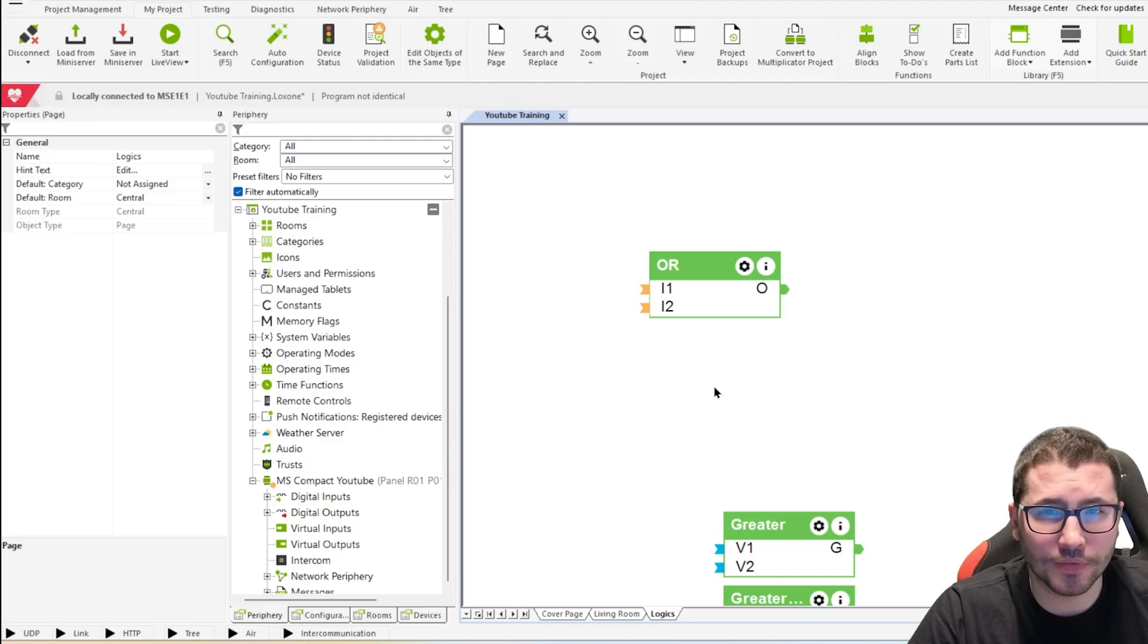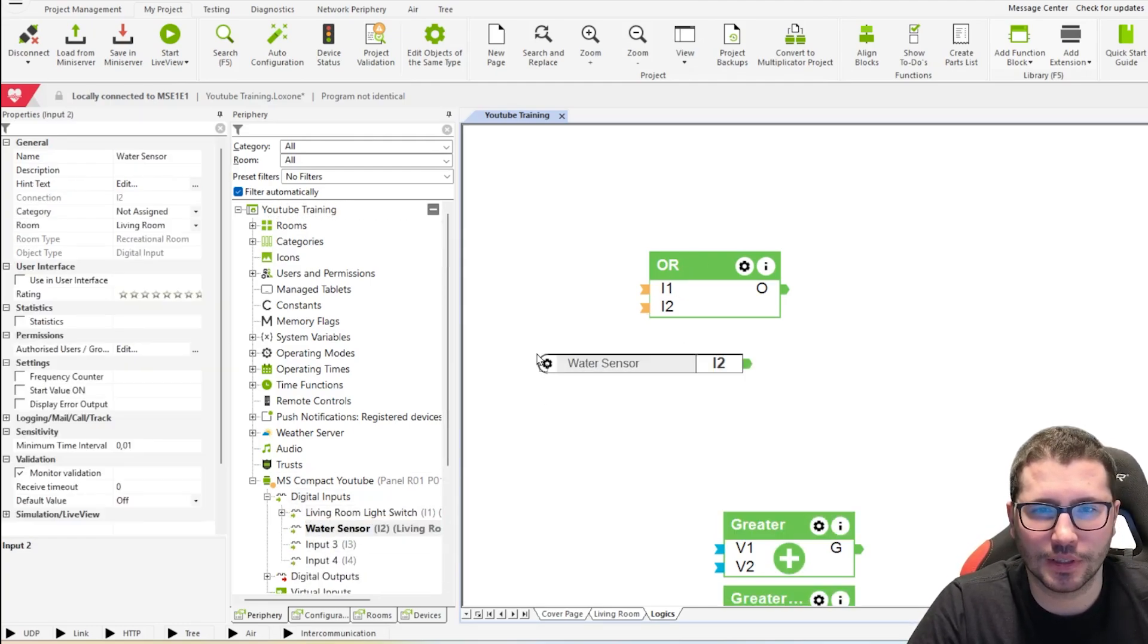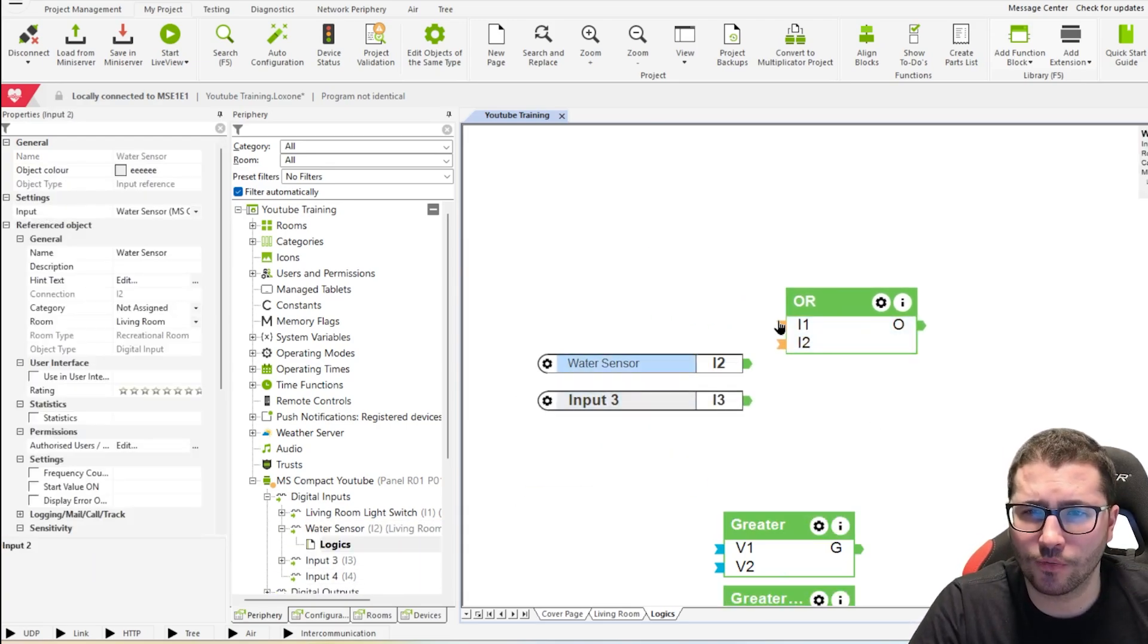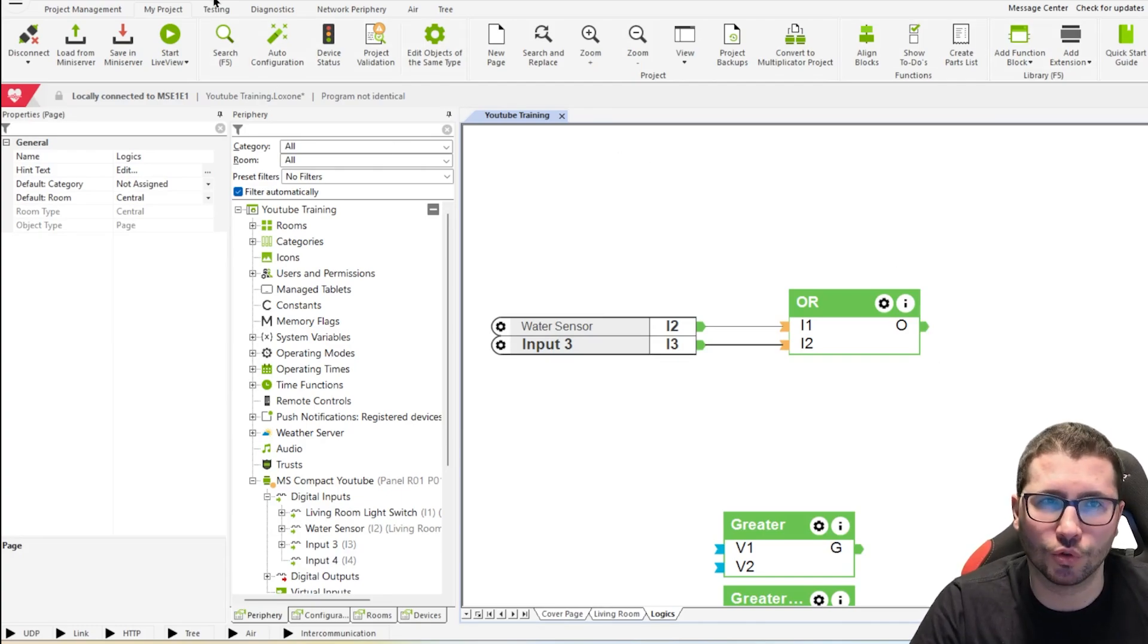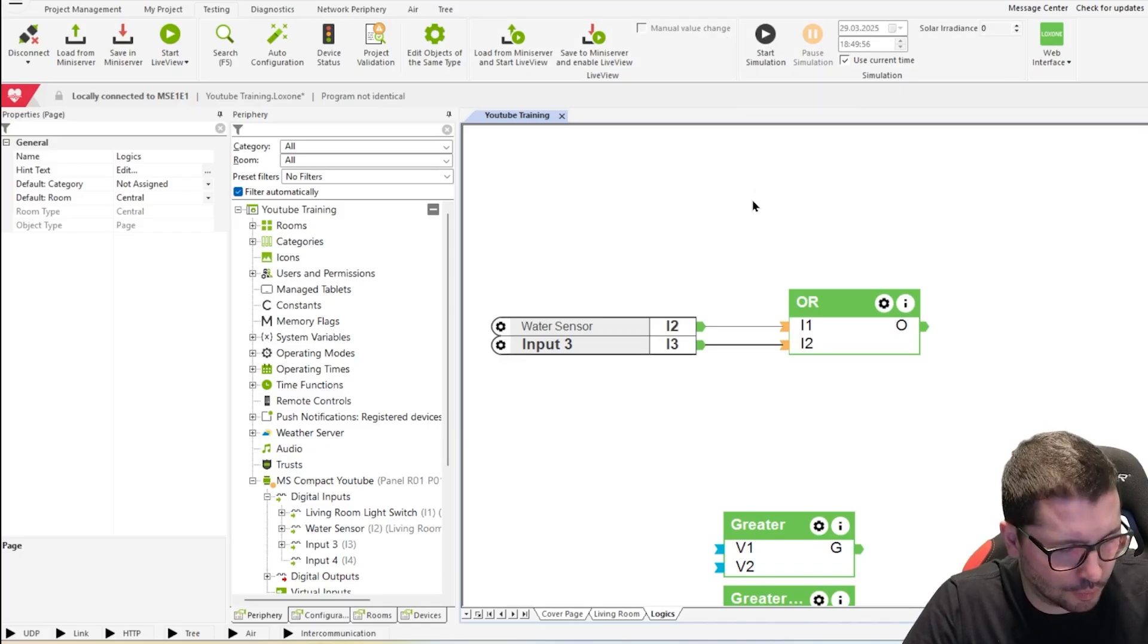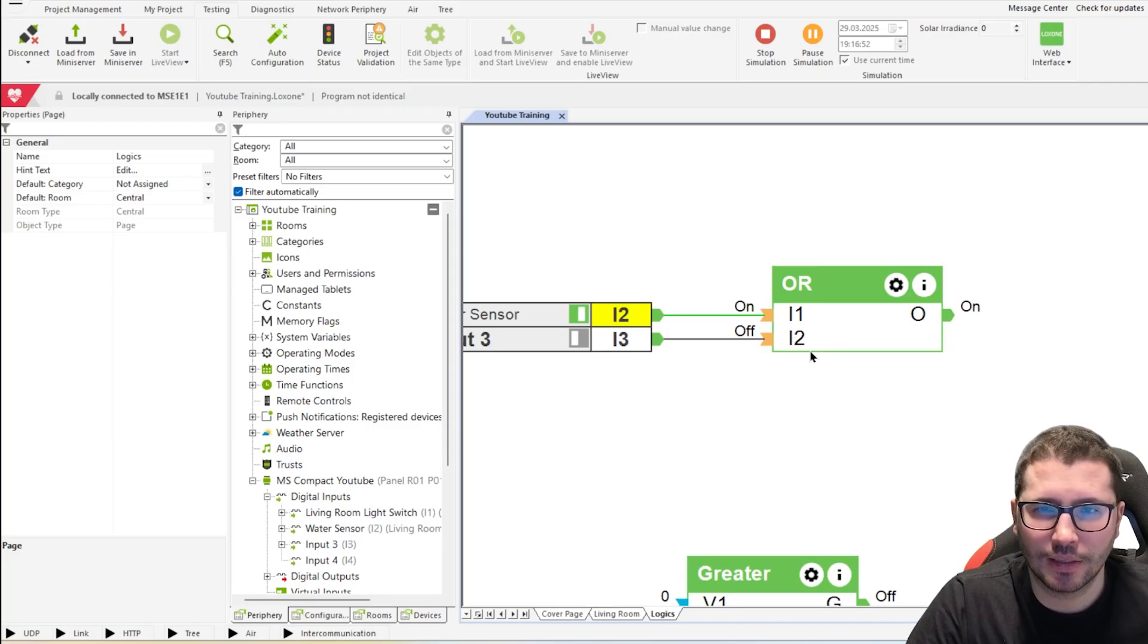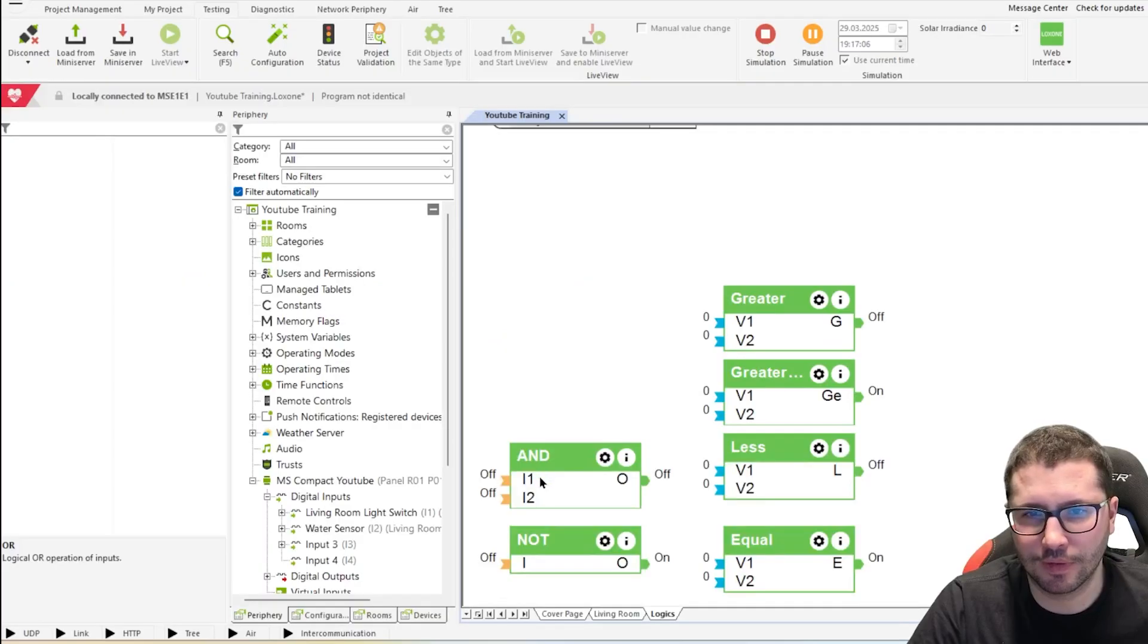Let's start with the first one. It's the OR function block. You could for instance say if there is this water sensor or the other water sensor, if one of those two is active, then you would like to make a water alarm. How to test this logic, there is a testing tab up here and then you can start the simulation or you can also press F7 if you're a real expert. Then you see there is an icon on the input that you can press and now you see either this sensor or that sensor or both. You have the output here permanently on.